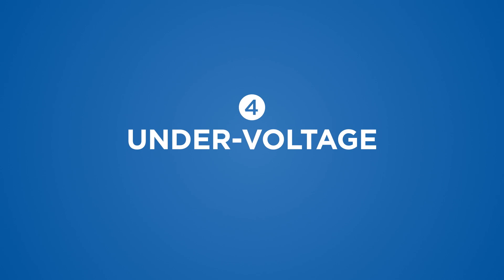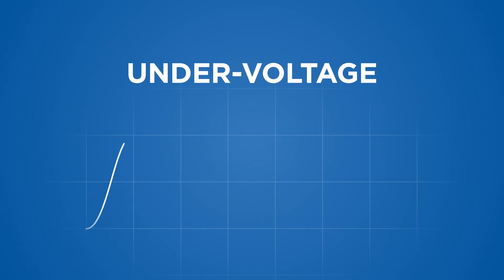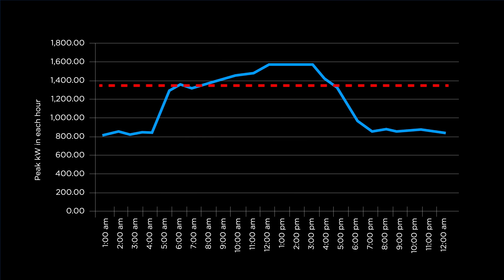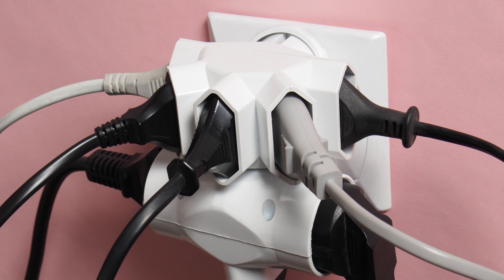The next two types of power problems are under voltage, or brownout: reduced line voltage for extended periods of a few minutes to a few days. This can be caused by intentional utility voltage reduction to conserve power during peak demand periods, or other heavy loads that exceed supply capacity.